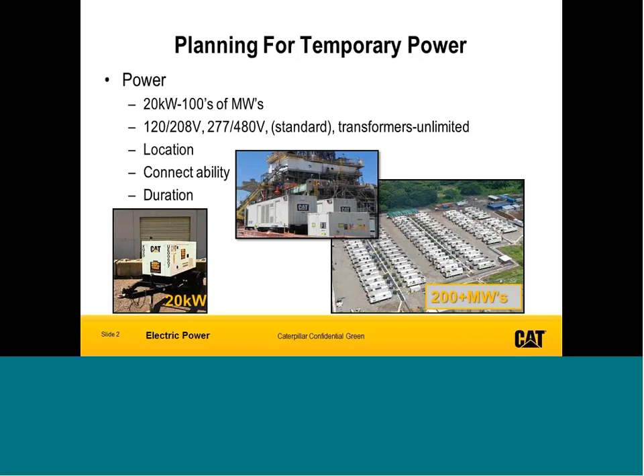Most manufacturers of smaller equipment, I'm talking 800 kW and below, will have switchable voltage between 480 volts and 220. The smaller sizes will have 120 or 208 volt available. Above 800 kW, it's going to be 480 volt standard, and a lot of times you'll have a transformer involved in order to step that up.